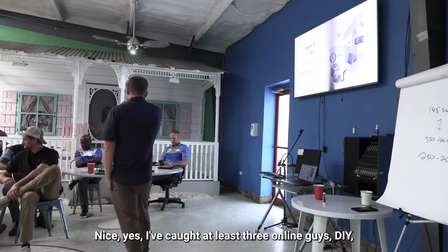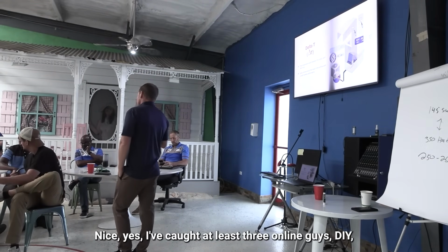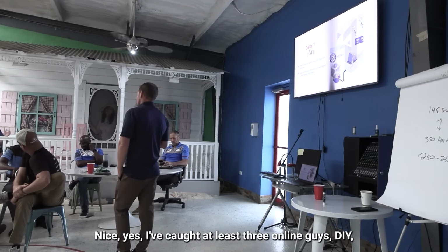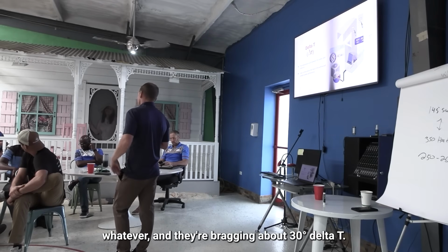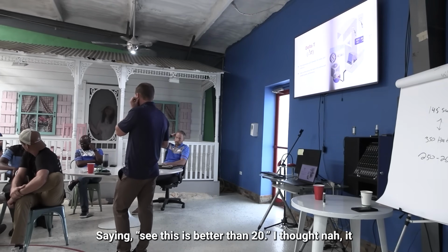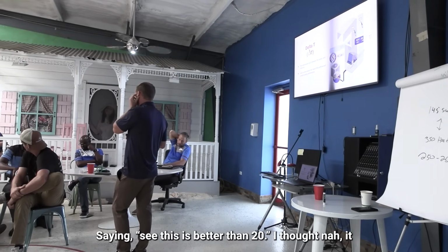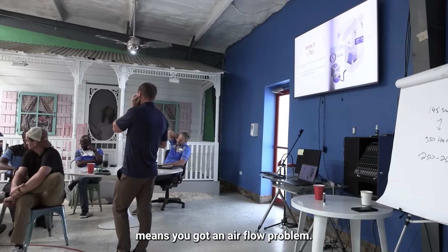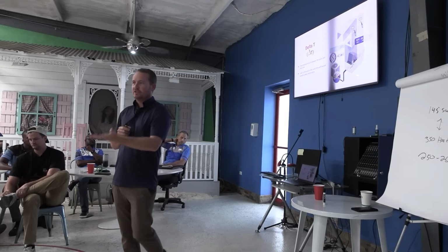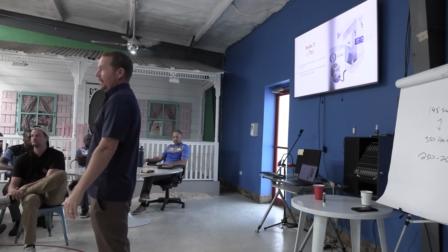Go ahead. Yes, I've got at least 3 online guys, DIY, whatever, and they're bragging about 30 degree delta T, saying, see, this is better than 20. Oh, no, that means you got an airflow problem. Means you got low airflow. And for those of you who don't get why that is, when you move the air slower over the evaporator coil, it gets colder. But that's all that is, right? So lower airflow means colder air.